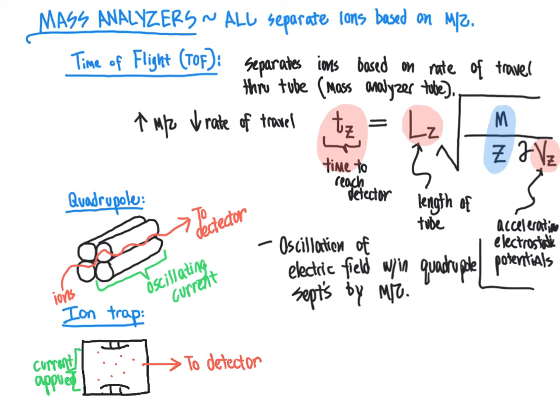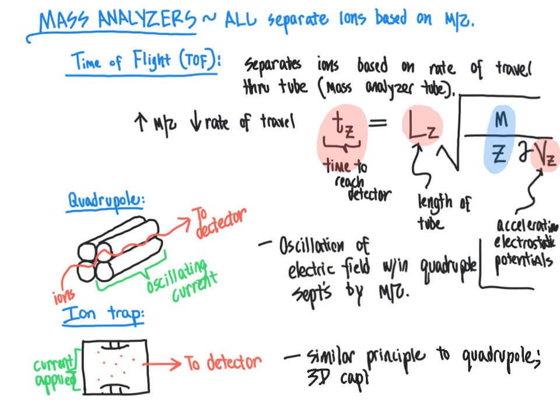The detector then detects those different ions exiting the instrument. As a summary: the ion trap operates on a similar principle to the quadrupole, as both rely on oscillating current to separate ions. The key difference is that the ion trap uses a 3D capture box where, at certain applied currents, certain mass to charge ratios are able to exit the trap, enter the detector, and generate the mass spectrum.